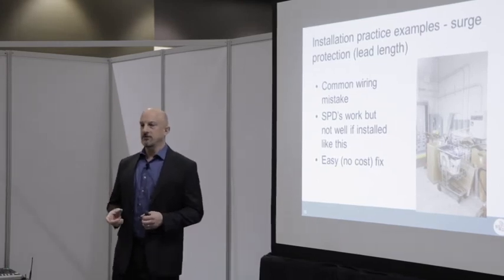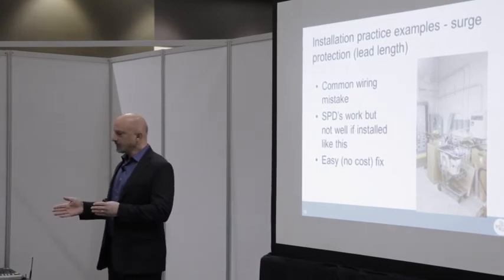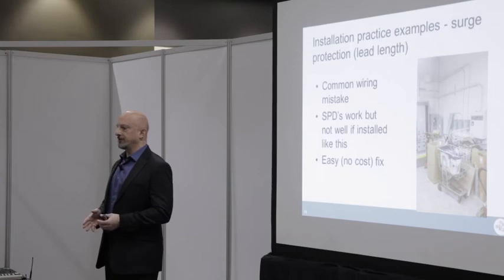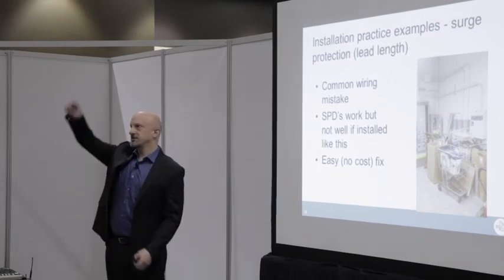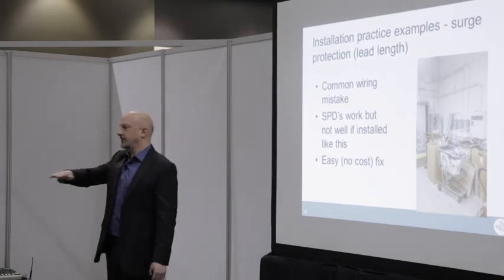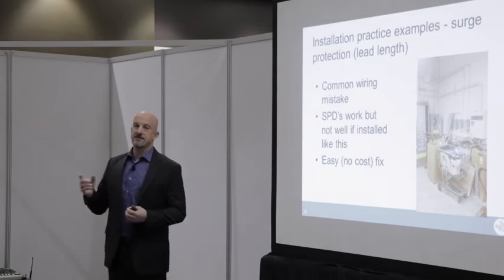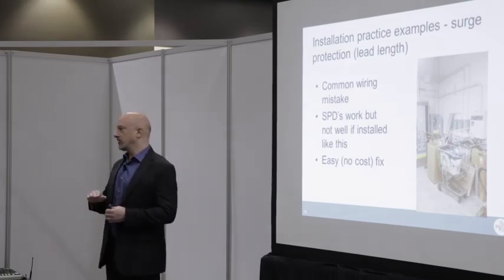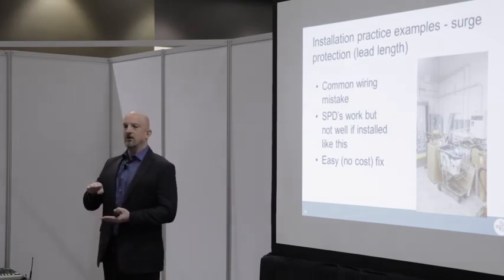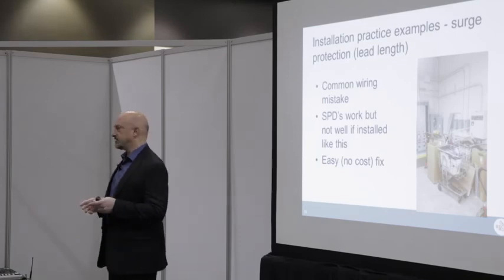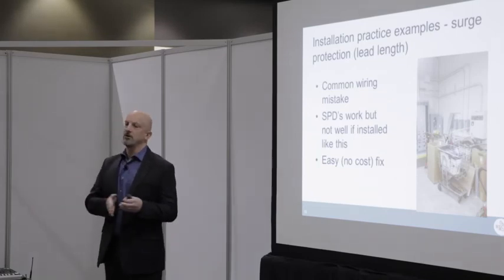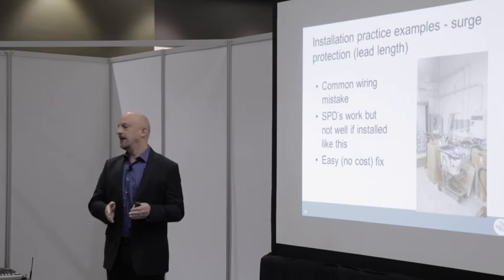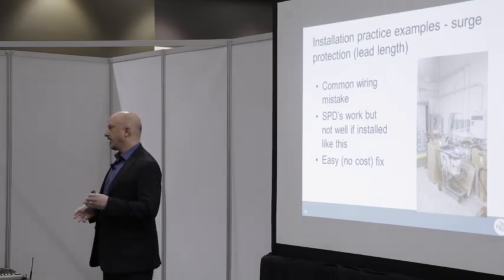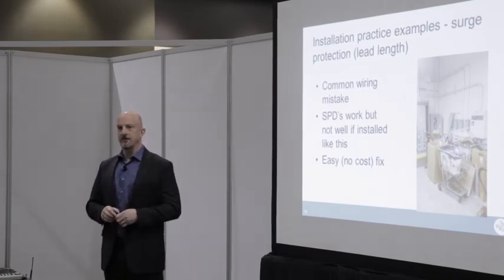If you install one in your house, the clamping voltage means that if the voltage goes to 7,000 volts, it'll cut it off at a certain level—say it clamps at 400 volts. That only works if the lead length is 6 inches, because that's how they test them. They test them all at a 6-inch lead length, and if you go longer, you've got to do your own testing.